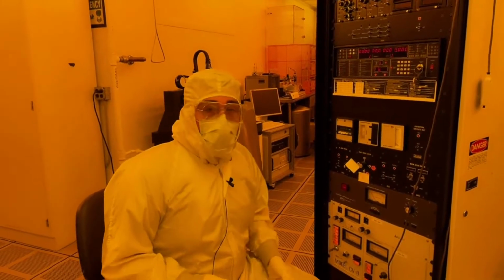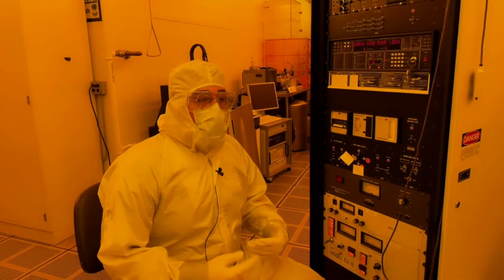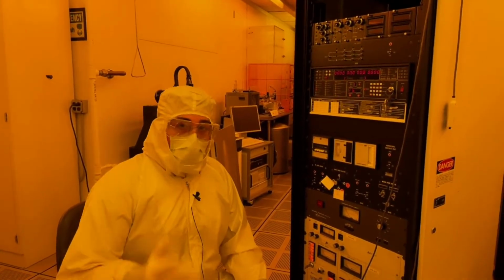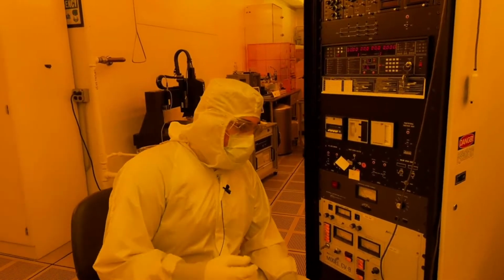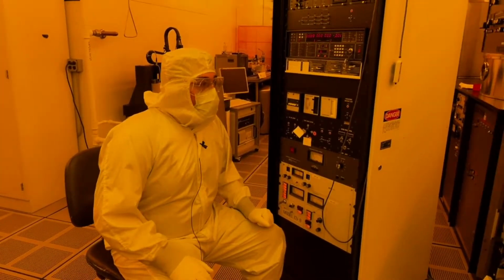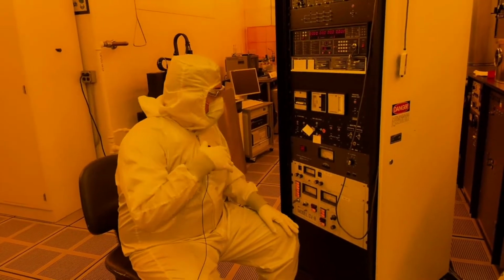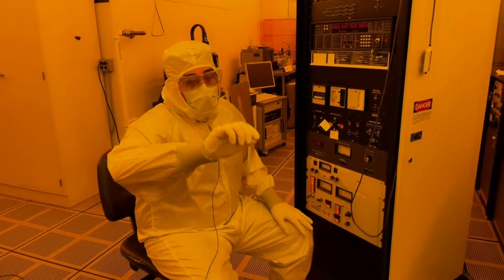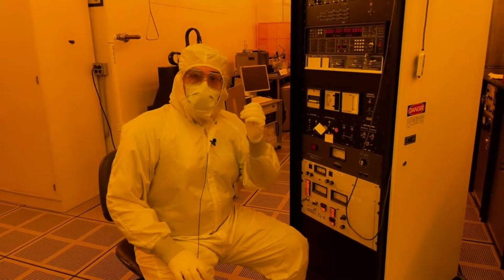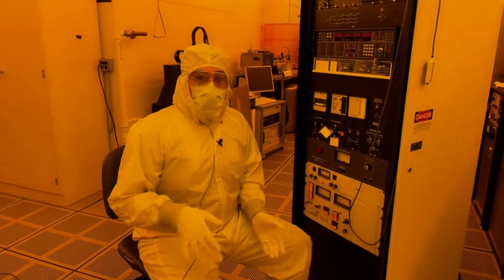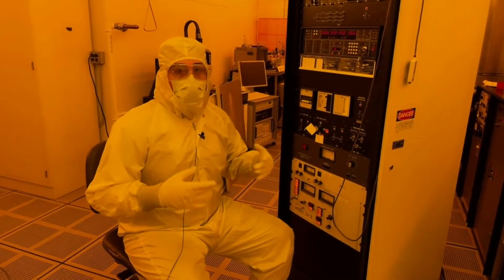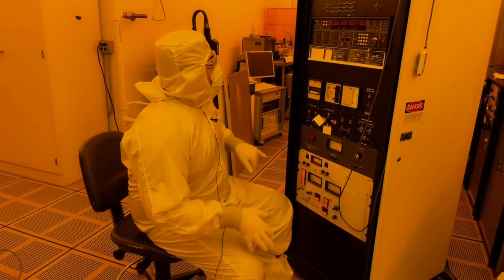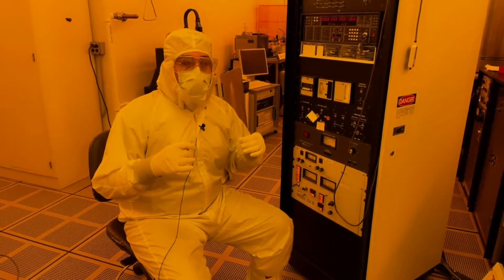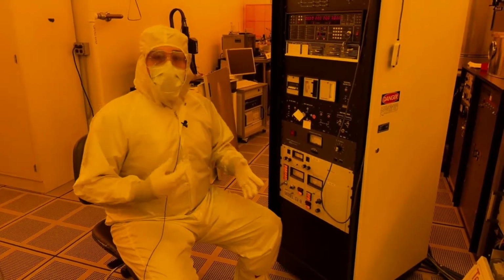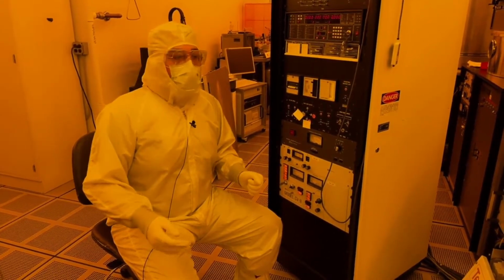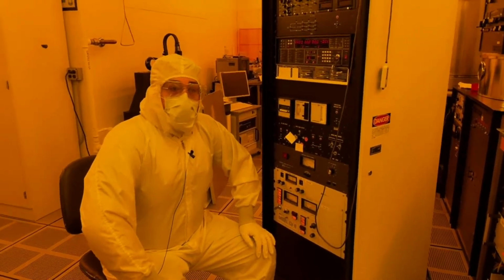There are other issues, of course, that could happen with it. If you have vacuum issues, it's always important to check all the pumps with a gauge that you know is working, check all the joints in the vacuum system, and determine where exactly the problem is. If you're having problems with the gun, it's always good to check every part of the gun: the high voltage source, the heating filament, and the tip. In any case, some of that stuff may be replaced, and usually that may be the end result of your troubleshooting. But in general, that's the easiest troubleshooting to approach, and stuff that we can actually repair in here without getting replacement parts. So that's mostly it. That's all the troubleshooting I have.